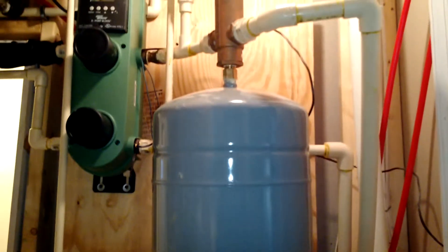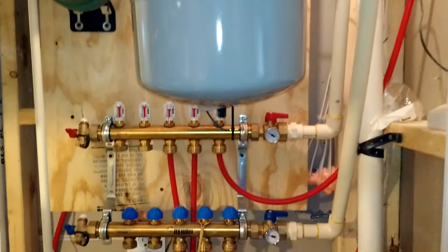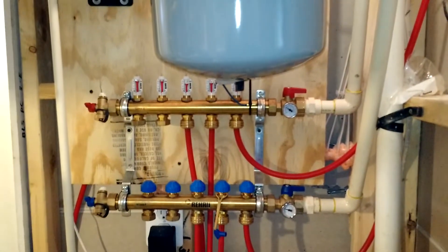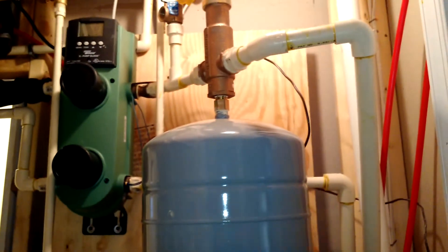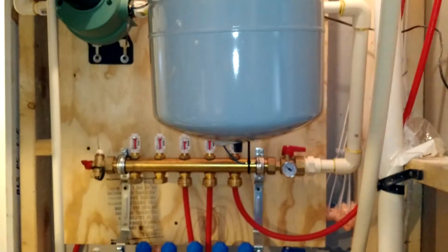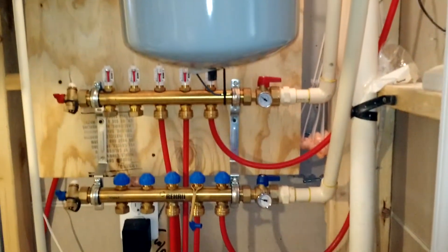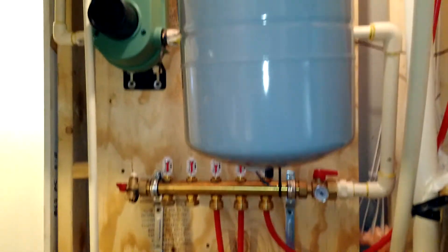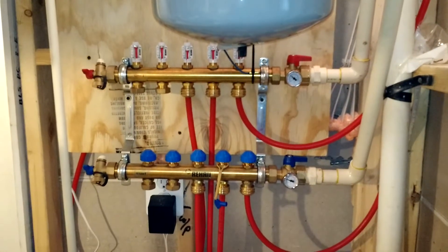So this is what I did to heat the floor. I got a Taco X-Block, I got a round manifold. I have two extra loops in case I ever want to do my garage. I just tied that manifold into the X-Block, into my water heater. So I'm pulling off my water heater, two heat exchangers, and then this is sending it through my floor. Right now I have my floor at about 95 degrees.